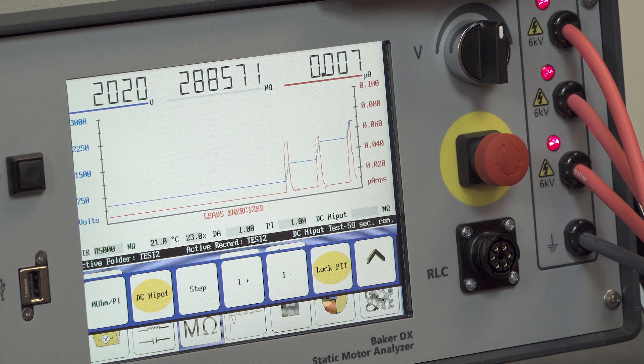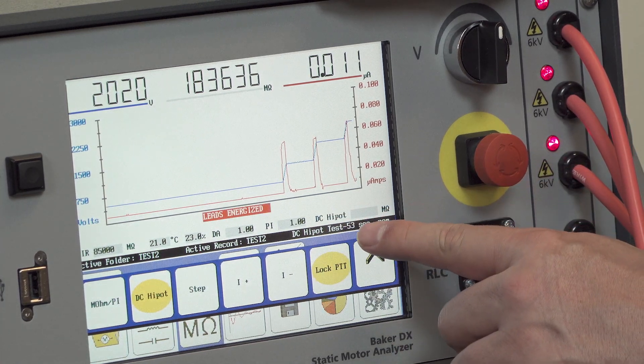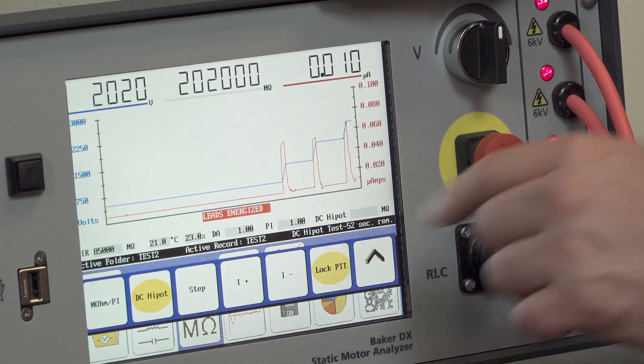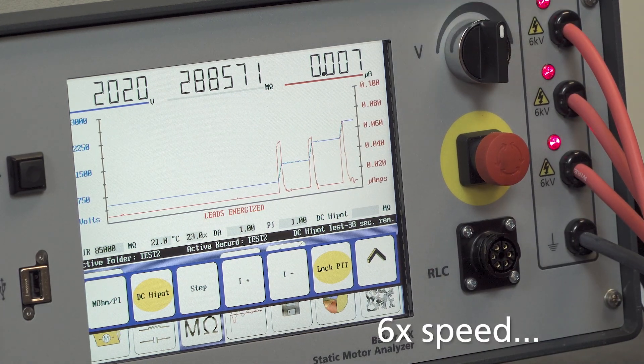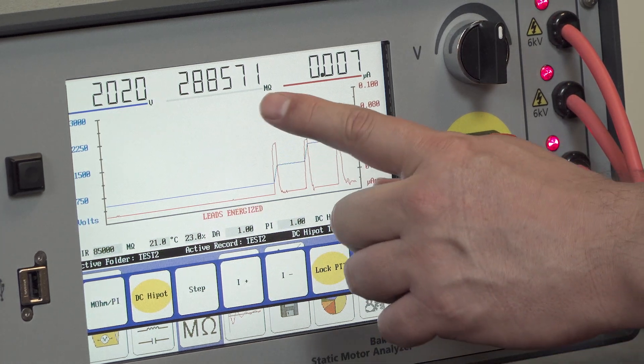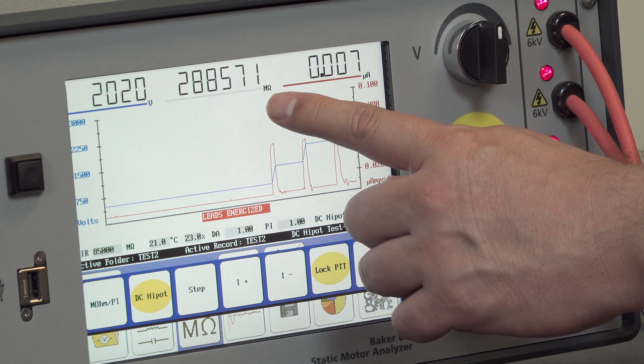And here on the right we see DC high pot test and the time ticking down from 53, 52 down to zero. Here in the middle we have the calculated insulation resistance value in mega ohms and the indicated measured leakage current in micro amps.